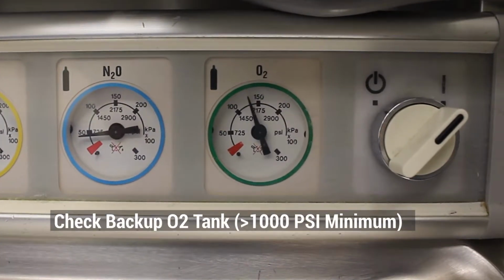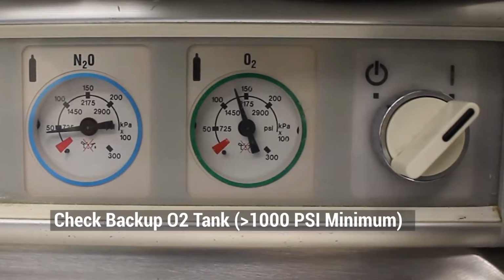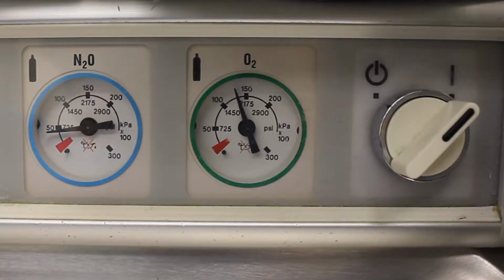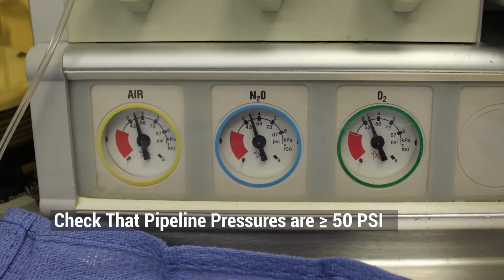Verify that a functional, adequately filled oxygen tank is connected to the anesthesia machine by opening the cylinder, observing the pressure, and then closing it. Verify that pipeline pressures are adequate.